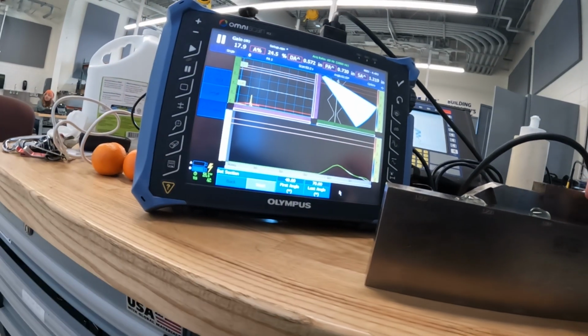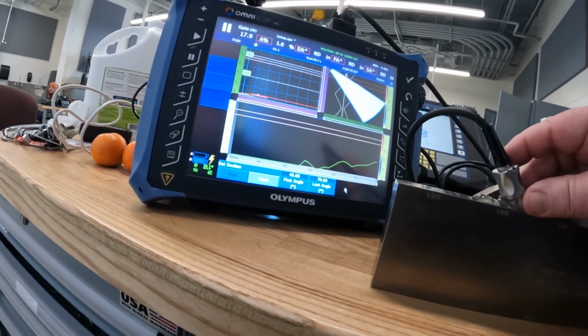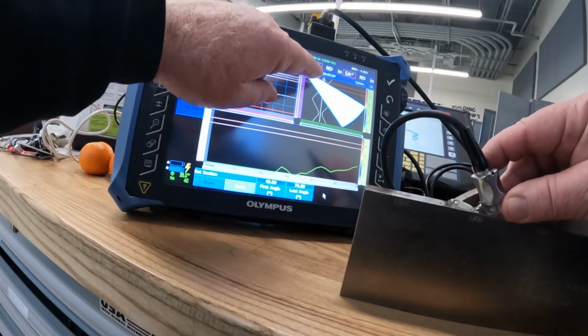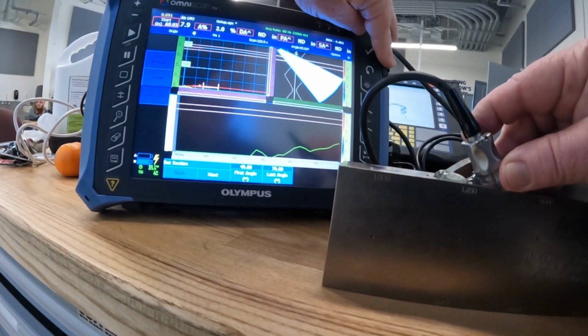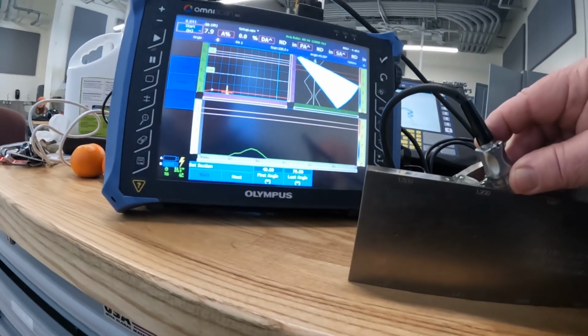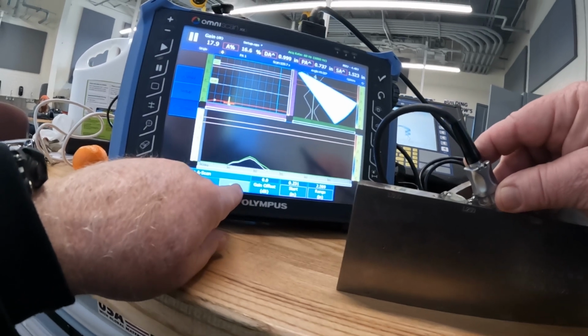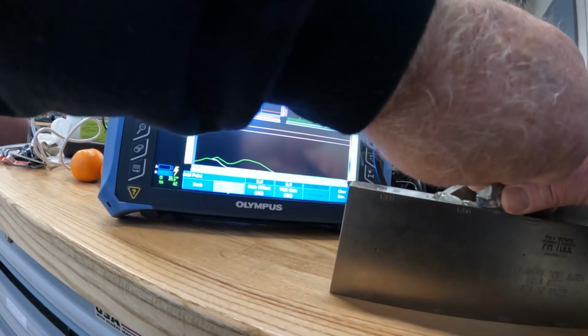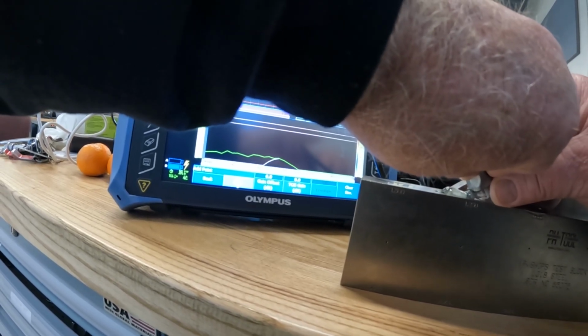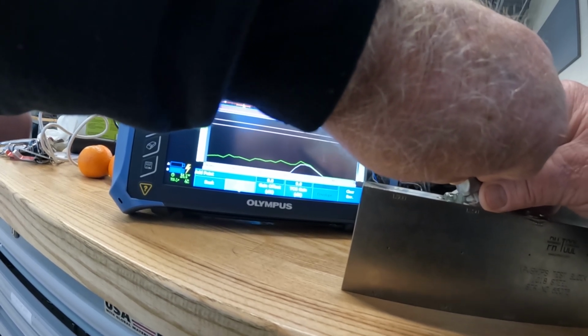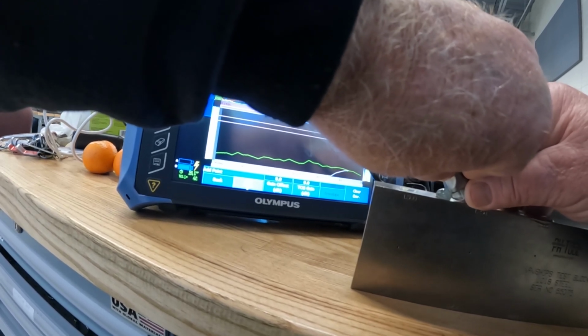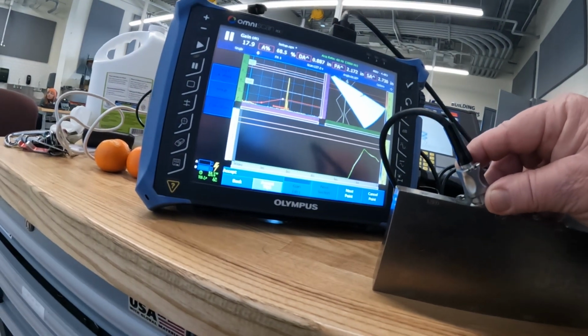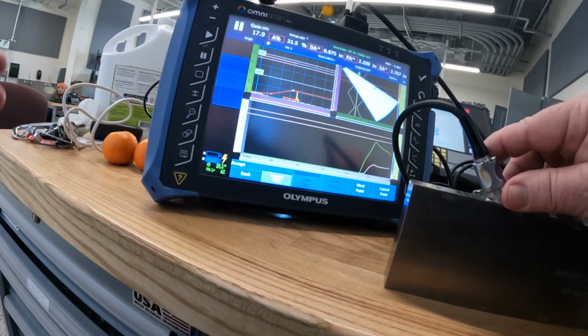Now the next point I'm going to be doing is actually the 1 inch reflector, and y'all can see it moving right there down below. So I have to move my gate down to it, and so I'll roll it down to there. And then now what I'm going to do is, again, I'm going to paint, hit next, next, it'll get to add point, and I want to add this point across the whole range. So it has to have a signal above the baseline all the way across. If it does not, then you have to increase the gain. If it goes over or it touches, it gets up to the high end, then you have a problem on the other side. So I've got the point, I hit next, and I've got the next point on my curve, you see? So it's picked up the first 2 points.